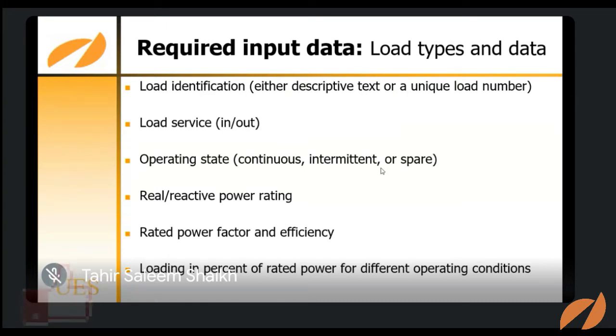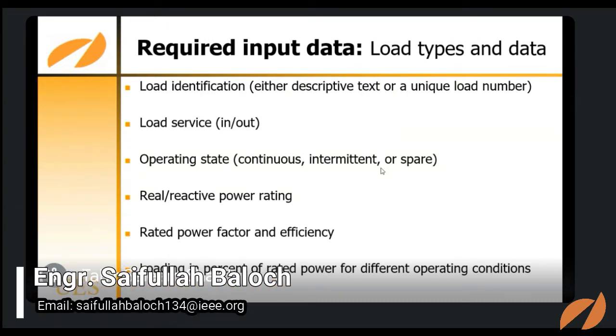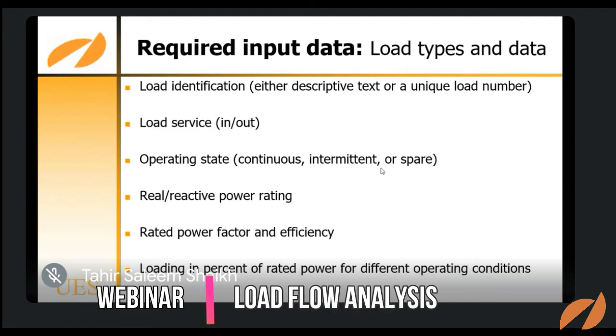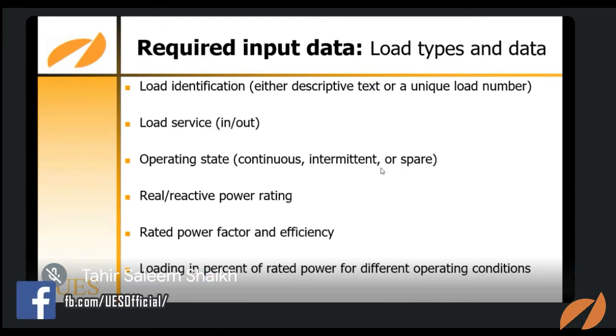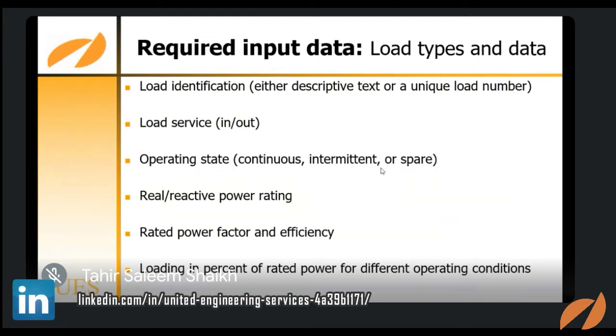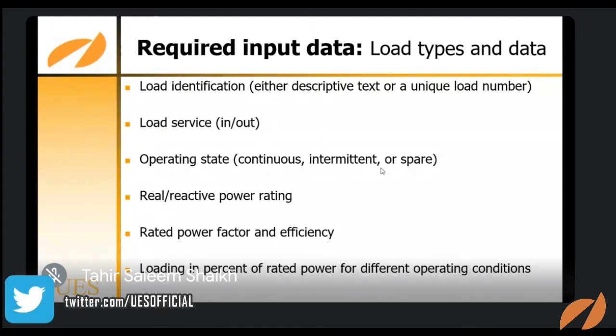Okay, loading in percent of rated power for different operating conditions. You will find this in computer based programs, where you are asked how much percentage of loading you want to put on that system. For example, if your load is 20 megawatt, then it will ask whether you want to put 80% of the load, 90%, or 70% of the load. This will also affect the efficiency, so if you have a low power factor or load factor, it will automatically decline your efficiency.